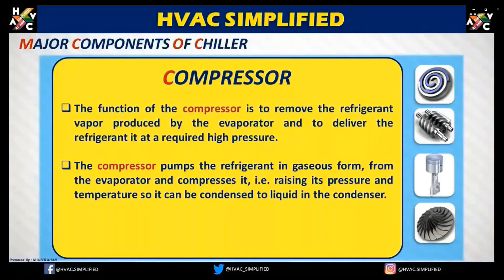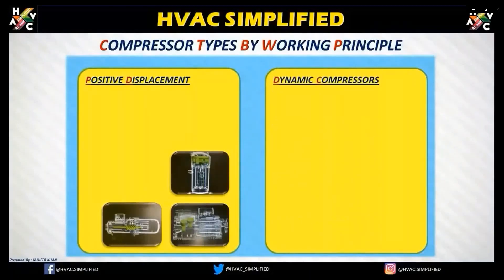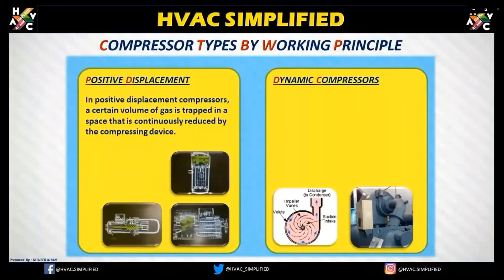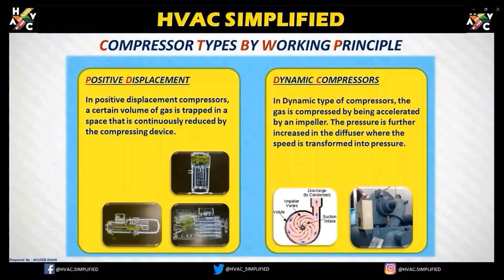I recommend you review the refrigeration cycle to understand what a compressor does in a complete refrigeration cycle. There are two major compressor types: positive displacement and dynamic displacement. In a positive displacement compressor, a certain volume of gas is trapped in a space that is continuously reduced by a compressing device. In a dynamic type, gas is compressed by being accelerated by an impeller, and the pressure is further increased in the diffuser where speed is transformed into pressure.